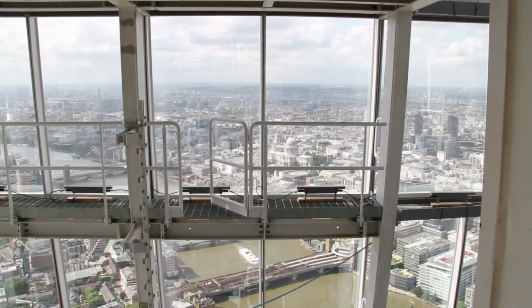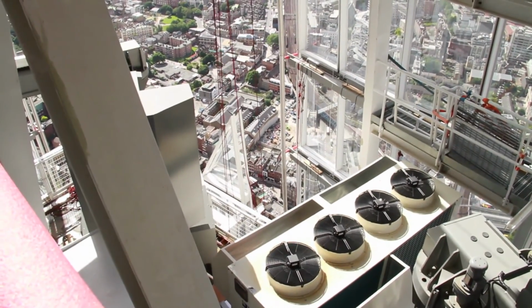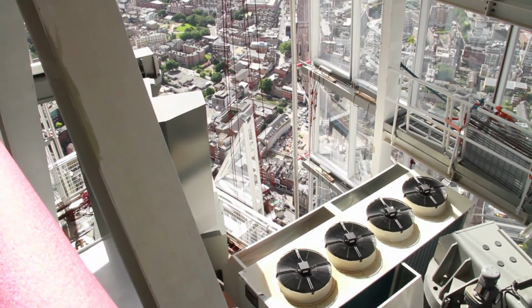Therefore, the cooling system that cools the lift motors must be extra resilient. For resilience, I've designed a completely standalone cooling system dedicated solely to the lifts and separate from the main system. The system is supplied by backup power and has two of every key piece of equipment, meaning if one fails, there's always another one on standby to tap in and take over.